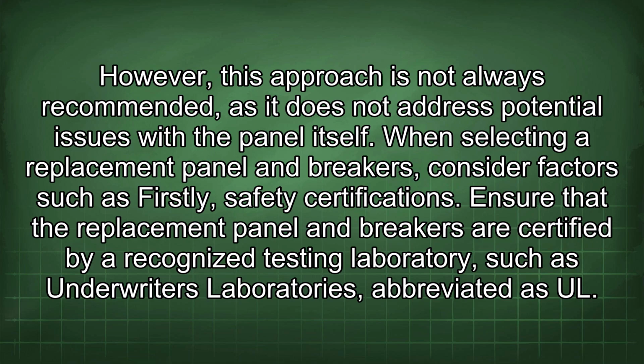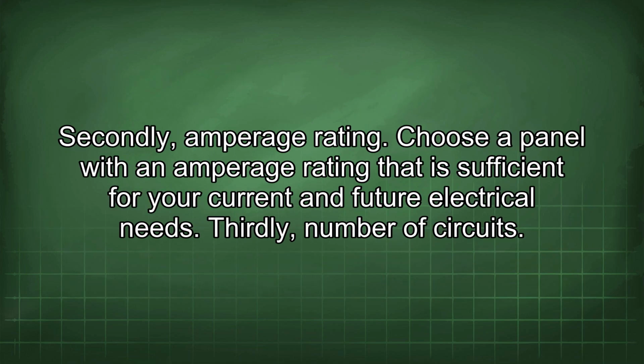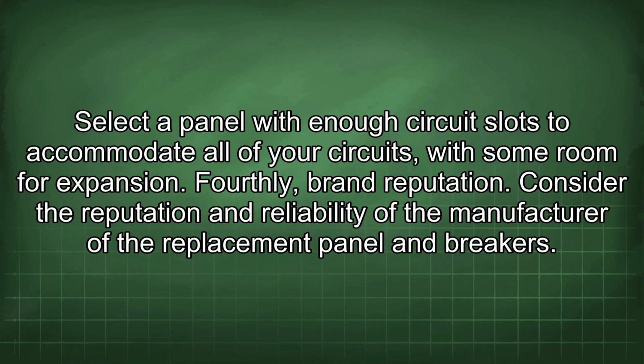When selecting a replacement panel and breakers, consider factors such as firstly, safety certifications. Ensure that the replacement panel and breakers are certified by a recognized testing laboratory such as Underwriters Laboratories, abbreviated as UL. Secondly, amperage rating. Choose a panel with an amperage rating that is sufficient for your current and future electrical needs. Thirdly, number of circuits. Select a panel with enough circuit slots to accommodate all of your circuits, with some room for expansion. Fourthly, brand reputation. Consider the reputation and reliability of the manufacturer of the replacement panel and breakers.